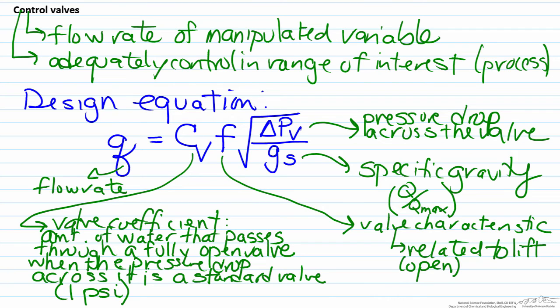We're going to talk a little bit more about the lift in just a minute, but an important point to note about this equation is that it is only valid for liquids. The reason why it's only valid for liquids is because gases being compressible causes an issue with the fact that we would need to know more information about the gas, particularly PVT information, in order to appropriately size the valve. Whereas in this equation we're assuming incompressible liquids, so it doesn't really matter the type of liquid we have or its temperature.